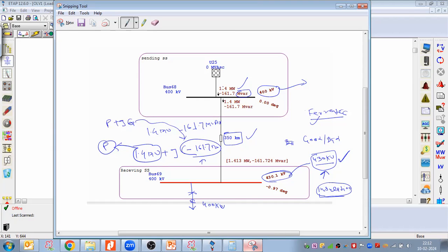Now you see the direction. So 1.4 megawatt is flowing through this circuit, right? But at the same time, the reactive power comes with a negative sign. When the negative sign comes, it means I am not withdrawing, taking or consuming this power from the grid. It is reverse, meaning I am injecting into the grid, feeding the grid. So anything that I am injecting into the grid comes with a negative sign. Am I clear with the sign?